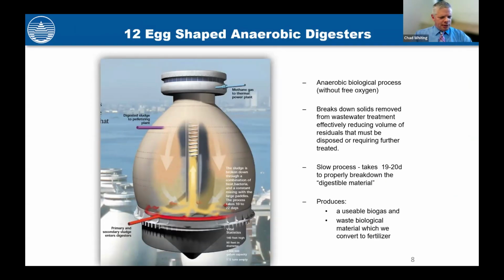We use a mesophilic process at 98 degrees. Our mixers are a draft tube center mixer that spans the whole depth of the digester. So we run that mixer at about 15,000 gallons per minute, and that turns over the digester about 7 times per day. I'm sorry, 15,000 gallons per minute, and it turns the digester over 7 times a day. So a lot of mixing.